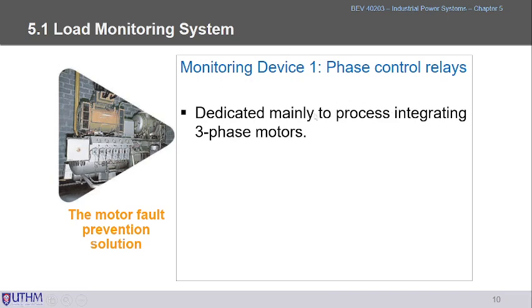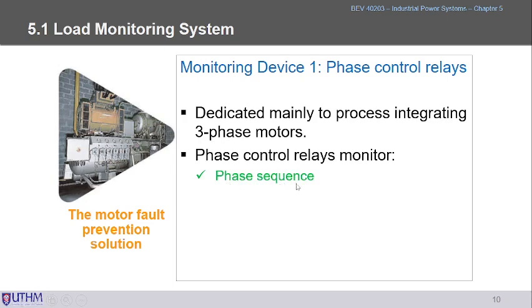This phase control relay is mainly dedicated to protecting three-phase motors. It will monitor the phase sequence. So what is the phase sequence? RYB, for example. Has the sequence changed, or is it in a healthy condition or not? Also the loss of one or more phases. Sometimes an overload happens at one specific phase, or it is due to an internal fault in the winding, for example, that makes one of the phases lost. That means the three-phase motor now operates on only two phases, with one phase lost. Then we can monitor it using the phase control relay.